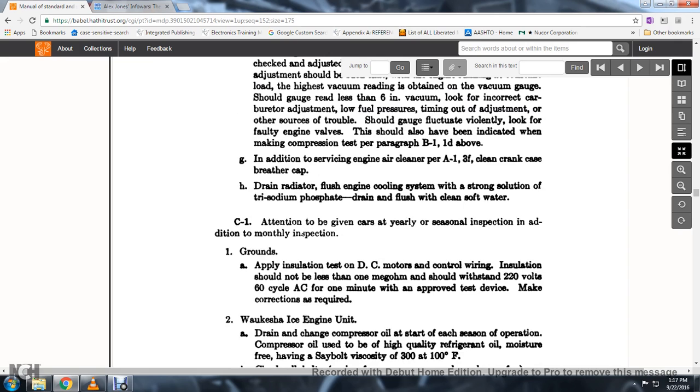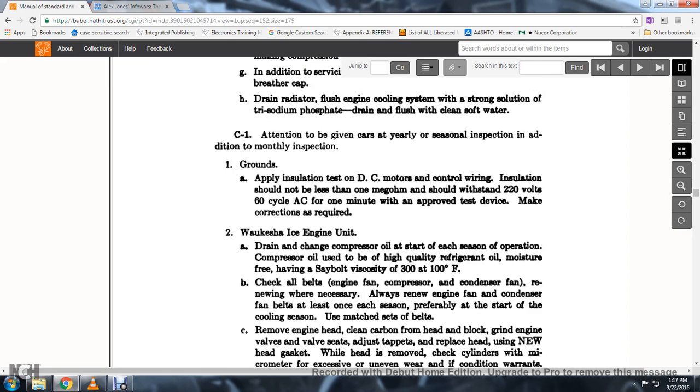C-1. Attention to be given cars at yearly: the seasonal inspection, in addition to the monthly inspection grounds. Apply insulation test to the DC motor controlling wire; insulation should not be less than one megaohm, and it should withstand 220 volts, 60 cycle AC for one minute with an approved test device, making corrections as required.